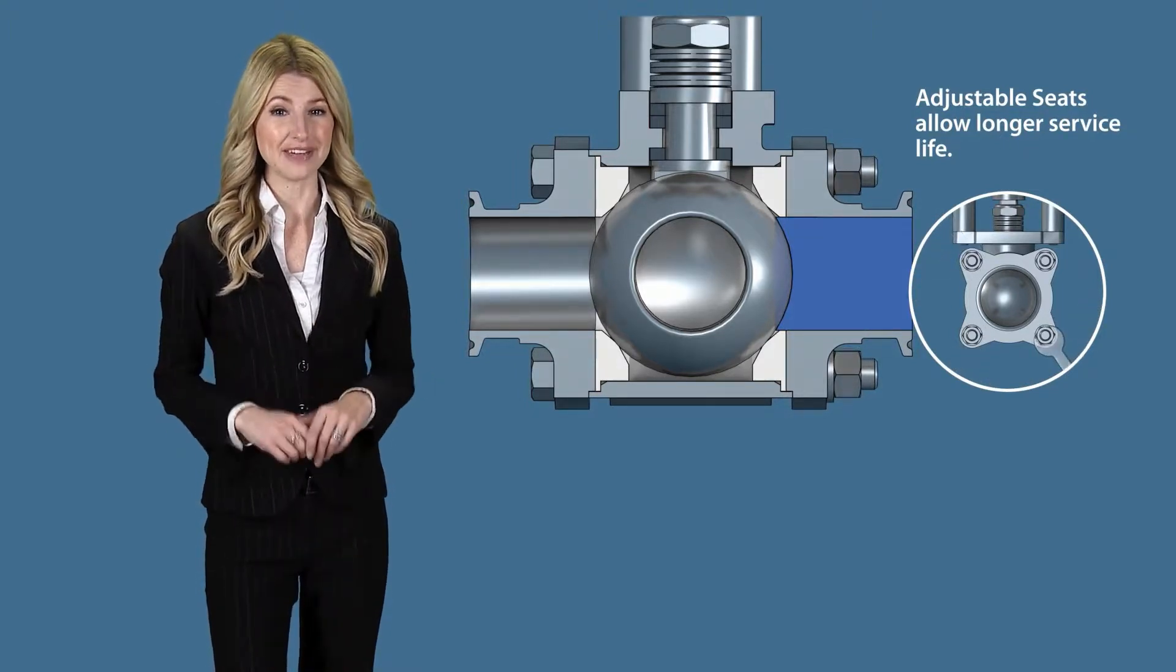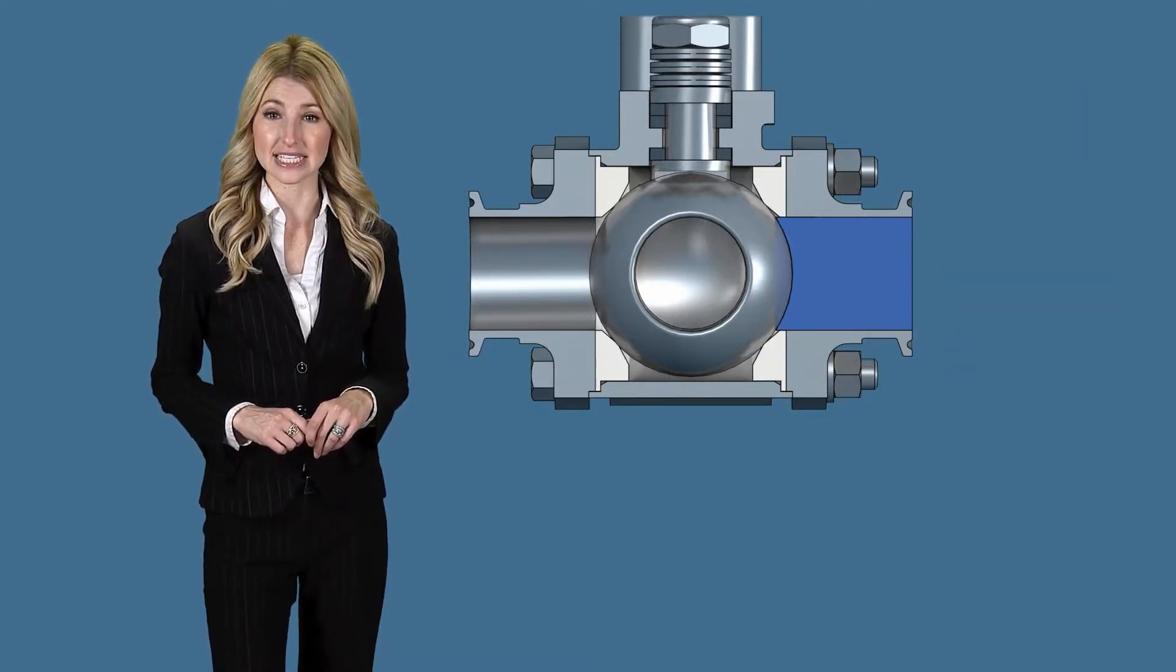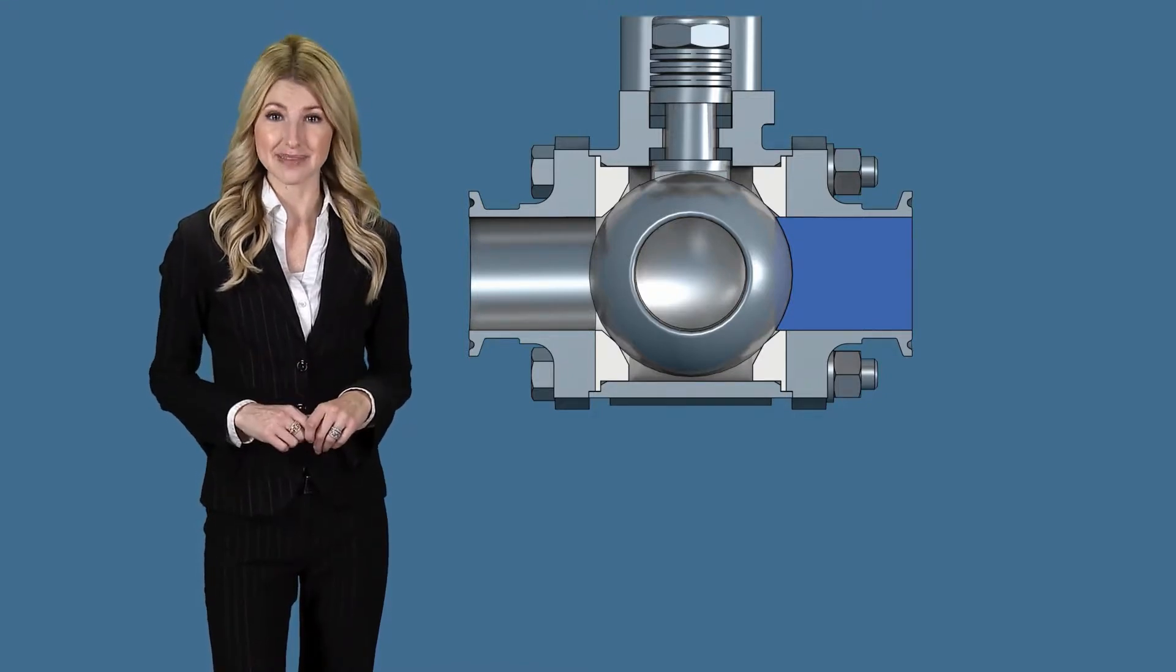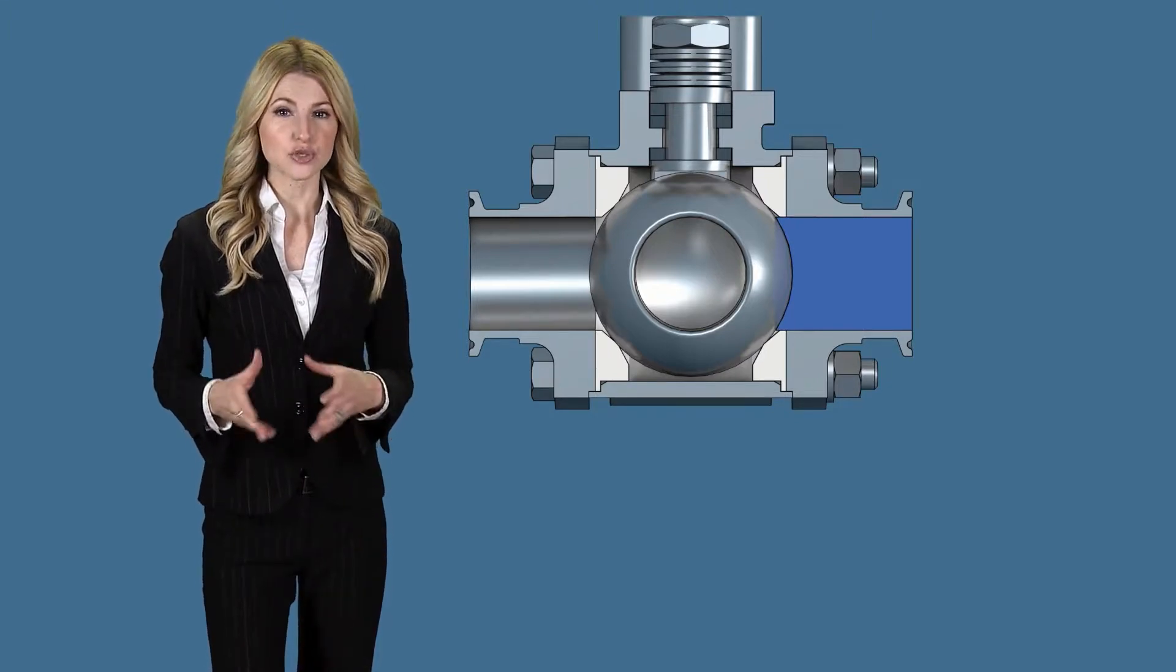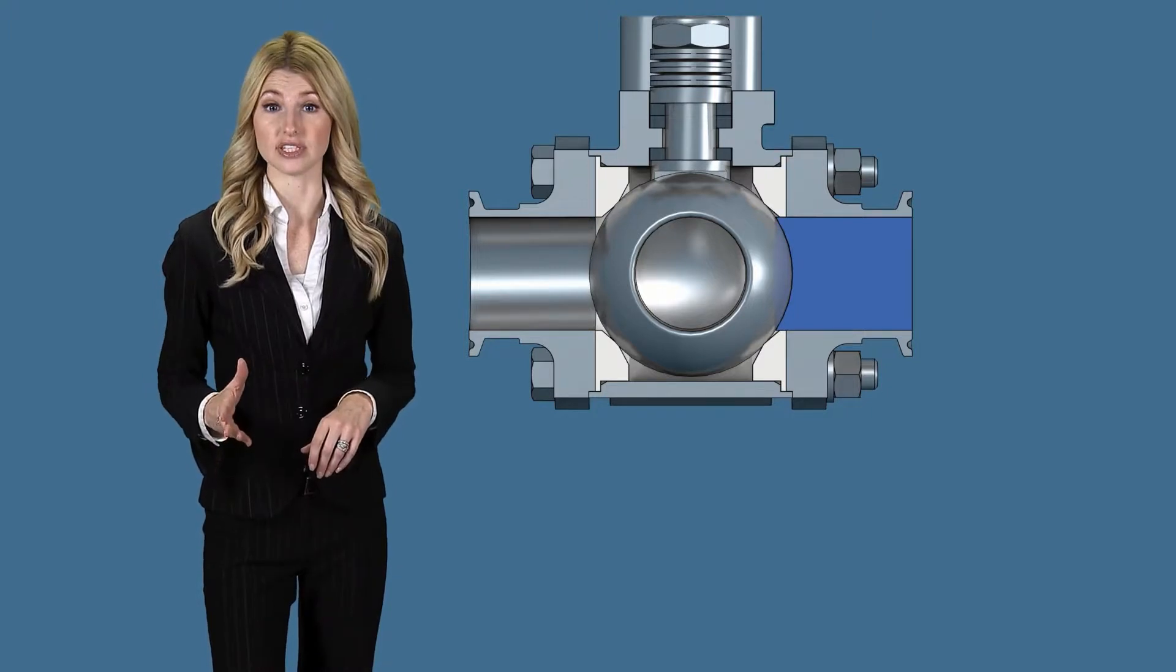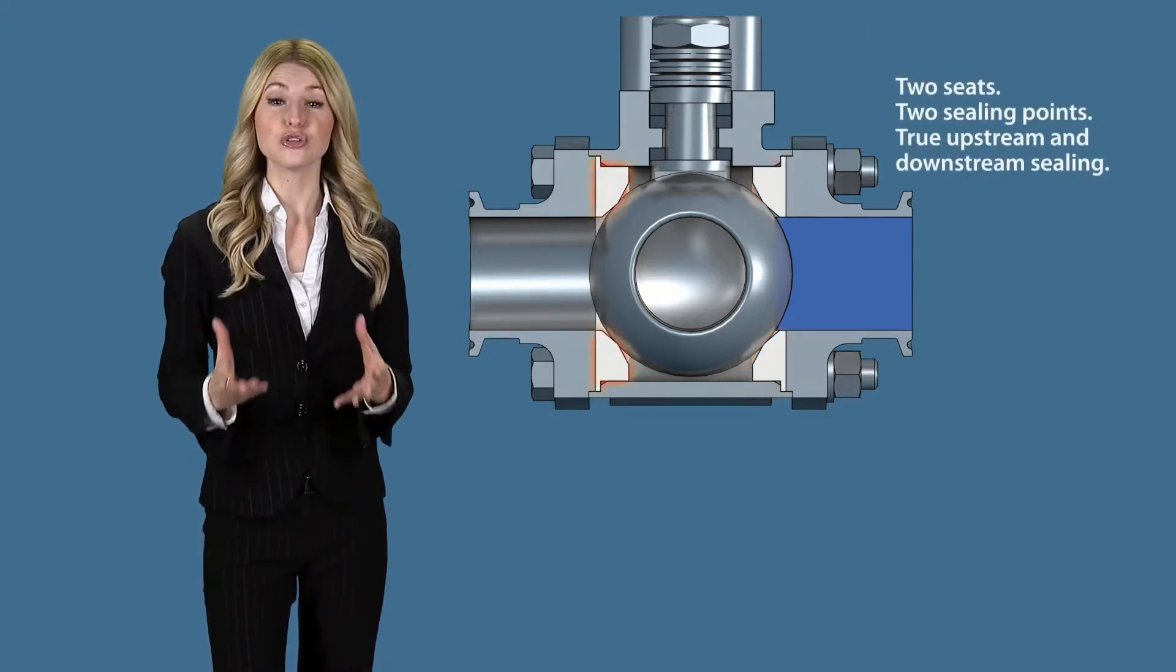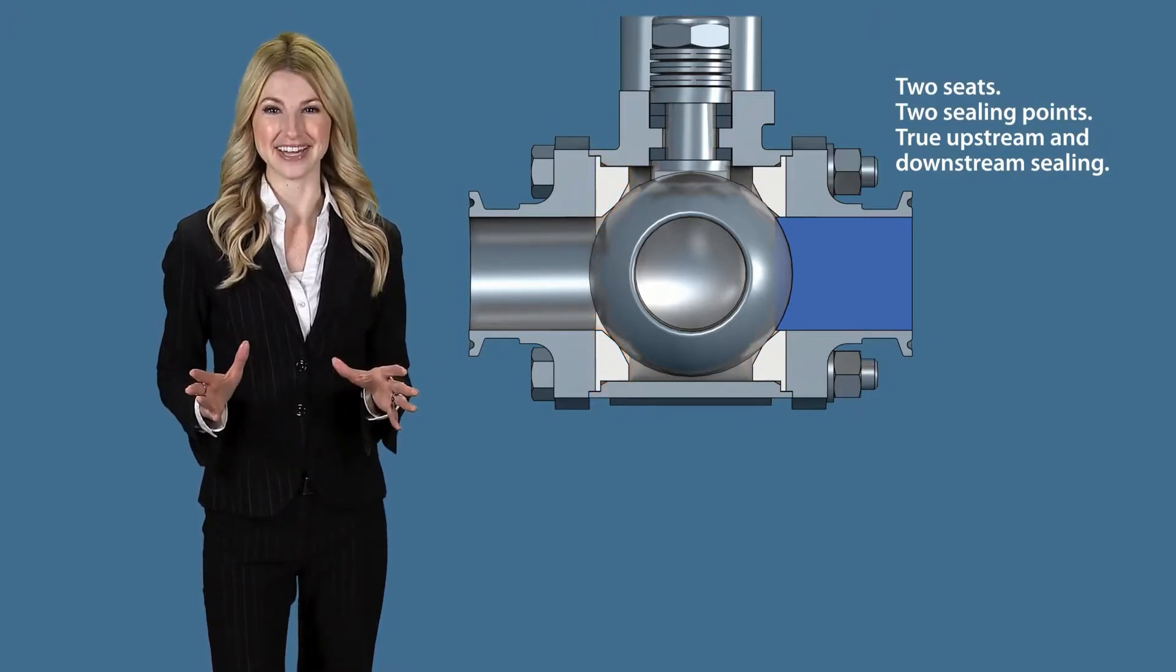But there's more you might find interesting. This technology works by having the ball compressed by the seats using the force of the valve body bolts, which provides a second benefit: an upstream sealing ball valve. Where traditional ball valves rely on upstream pressure to float the ball to the seats, we bring the seat to the ball. Two seats, two sealing points. True upstream and downstream sealing. Simply innovative.